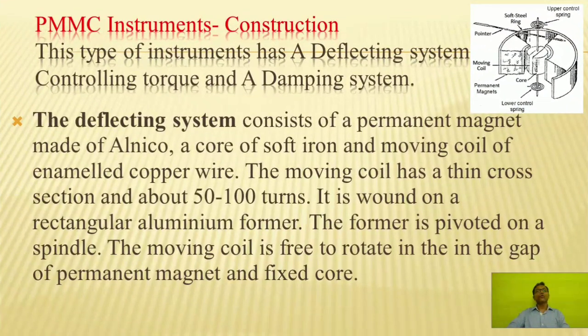We will now see the construction of a PMMC type instrument. This type of instrument has a deflecting system, controlling torque, and damping system. The deflecting system consists of a permanent magnet made of alnico, a core of soft iron, and a moving coil of enameled copper wire. The moving coil has a thin cross-section and about 50-100 turns. It is wound on a rectangular aluminum former, which is pivoted on a spindle. The moving coil is free to rotate in the gap between the permanent magnet and the fixed core.